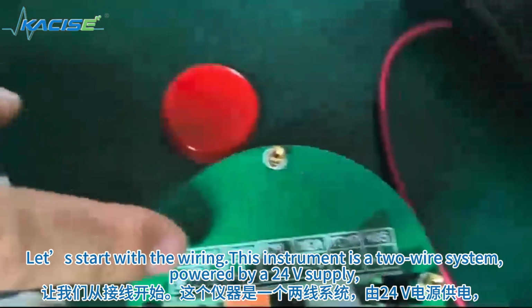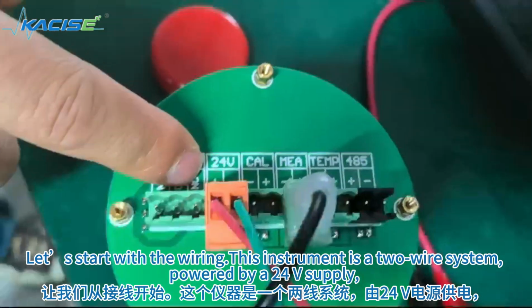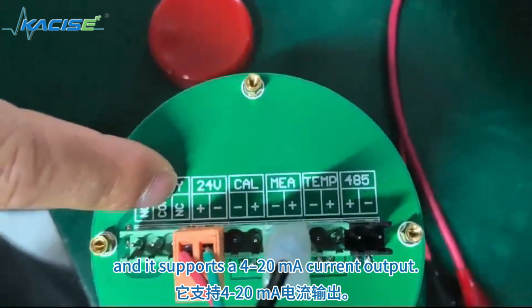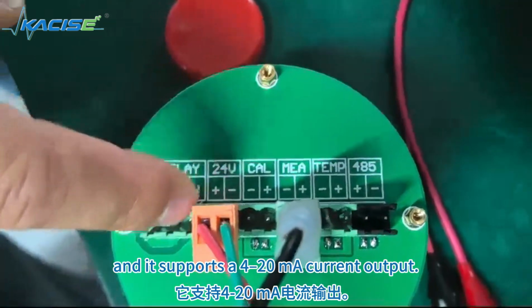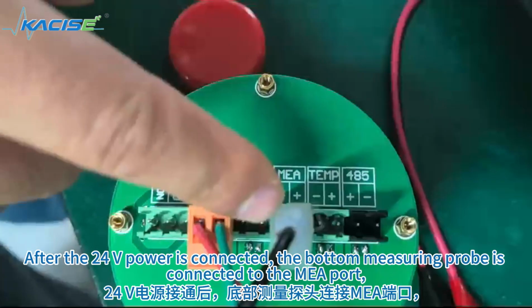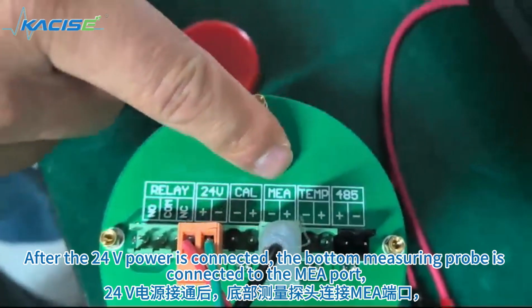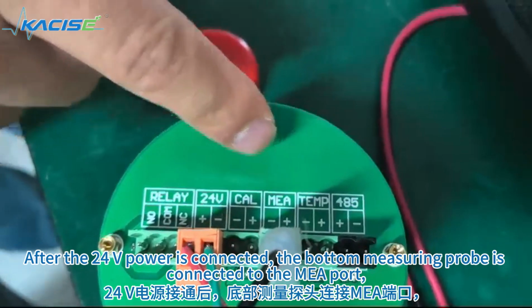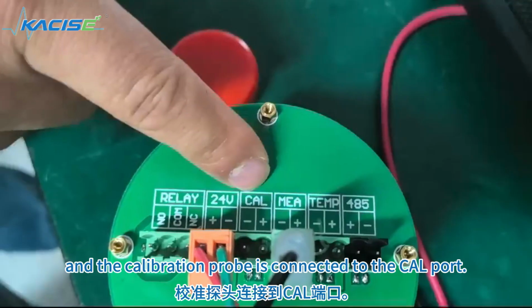This instrument is a 2-wire system, powered by a 24-volt supply, and it supports a 4 to 20 mA current output. After the 24 volts power is connected, the bottom measuring probe is connected to the MEA port, and the calibration probe is connected to the CAL port.